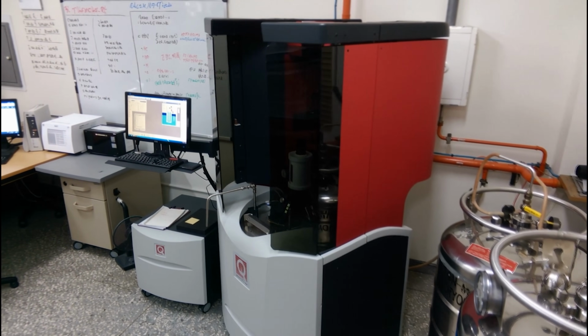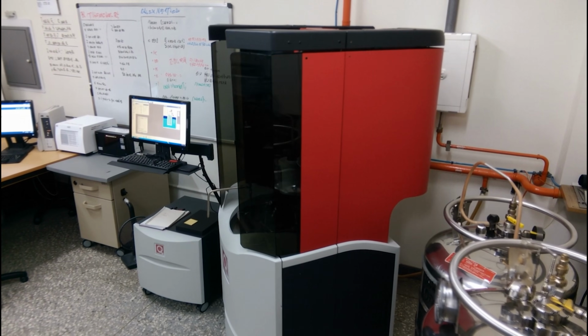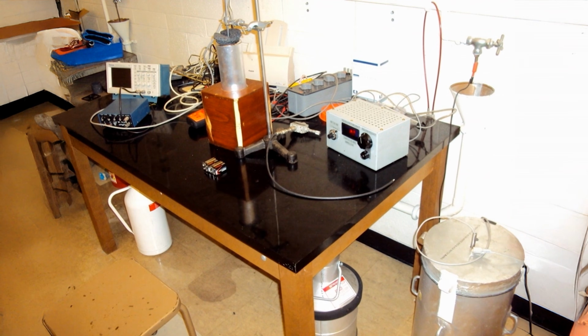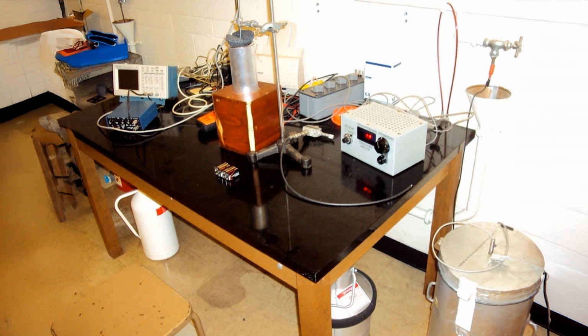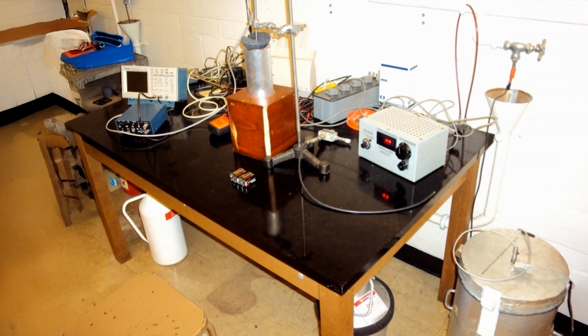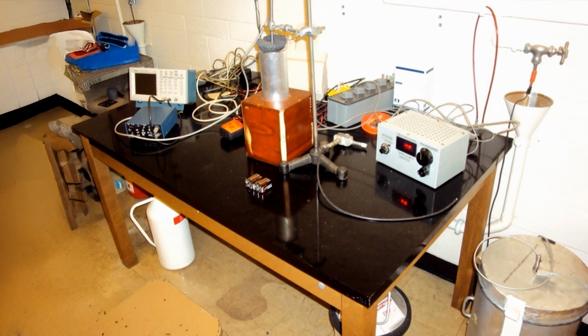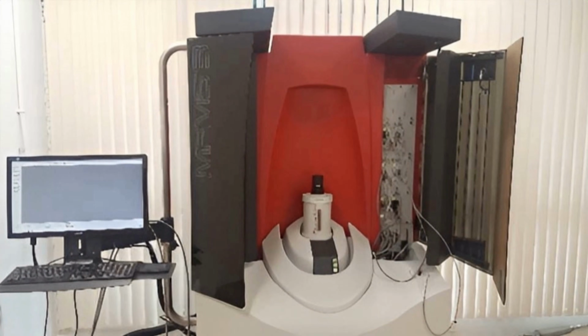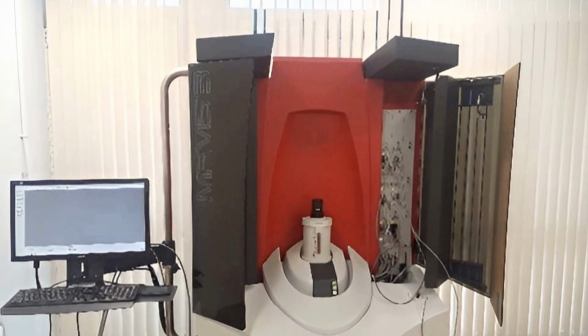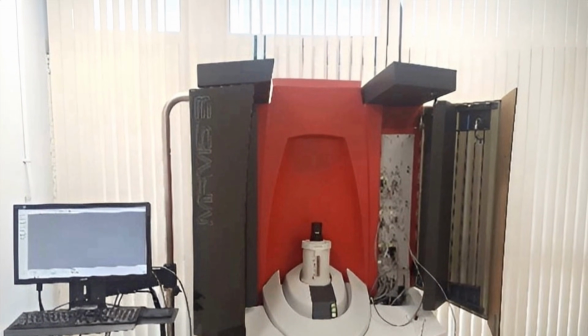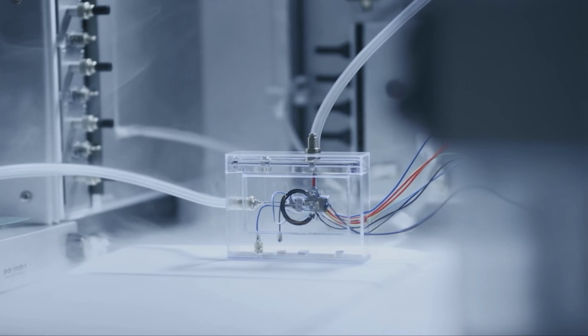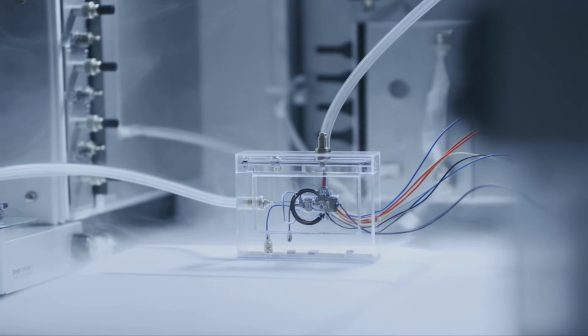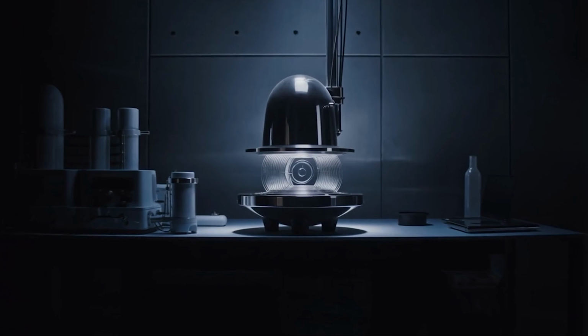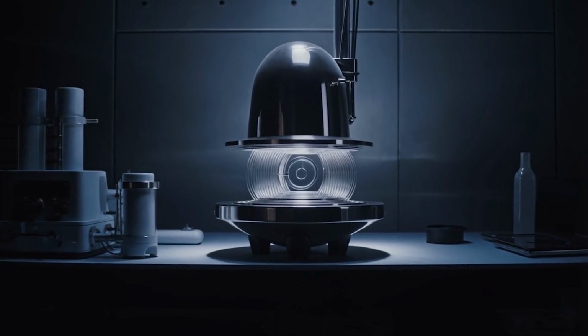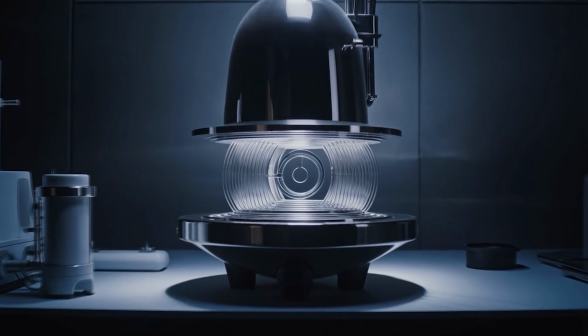Now, this change produces a measurable variation in voltage even when the magnetic field is extraordinarily weak. And because of this, squids can detect changes in magnetic flux as small as a few femtoteslas. Yeah, that's pretty small. Now, to function properly, these have to be cooled to cryogenic temperatures, often using liquid helium. That requirement makes them large, complex, and expensive compared to most sensors. And despite that, though, they're used extensively because no other device offers comparable sensitivity.